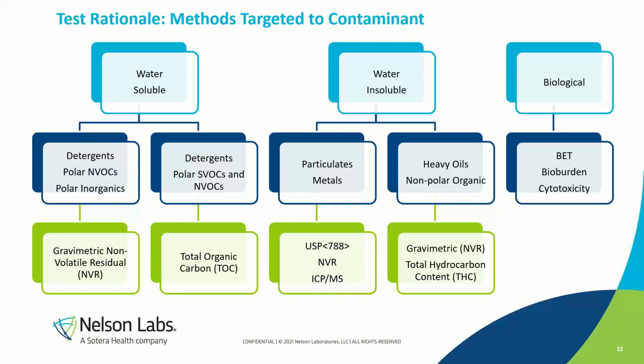The other option is NVR. We kind of talked about that earlier with the water soluble column. Gravimetric will pull off those particles as well. So if you have a device and it has detergent on it, and it also has metal particles, then that's both going to come off in the gravimetric extraction and just kind of be one lump sum of mass. With the USP 788, that's going to give you a count of particles based off of particle size of those metal particulates.